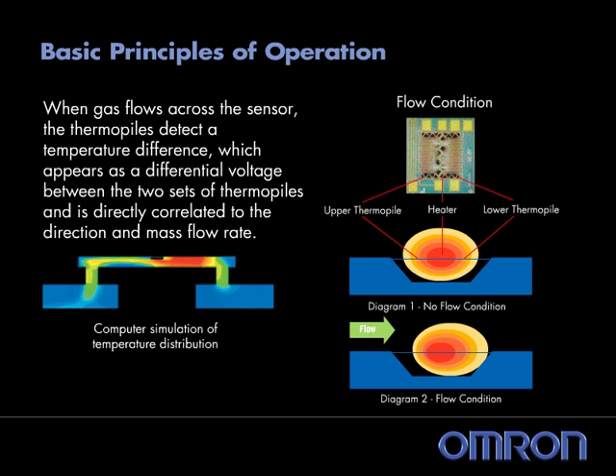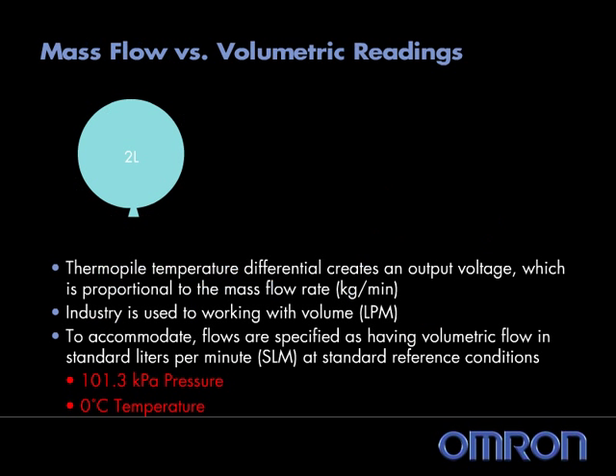As air flows across the MEMS Flow Sensor Chip, a temperature differential is created between two sets of thermopiles. This differential is signaled by an output voltage proportional to the mass flow rate of the gas flowing over the chip.